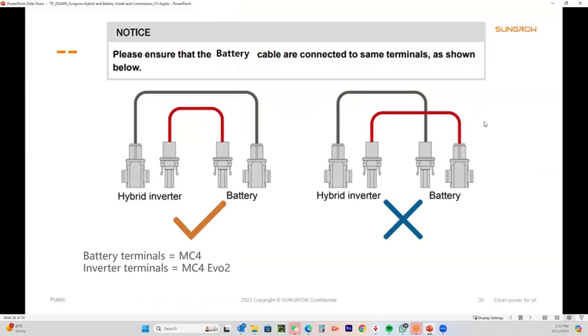Now, on the power cable between the battery and the inverter, it's a parallel connection, so you're going positive to positive and negative to negative. If you do positive to negative and connect it up, when you switch the inverter on you'll get the red fault light. It won't blow up or anything, it'll just show a fault, and the fault code is incorrect polarity. So bear that in mind.